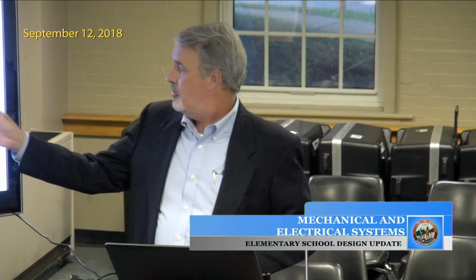Again, an overhaul, an integration into controls. So on those two schools, one of the things we talked about is overlaying a VRF system into the classrooms. Imagine these boxes are classrooms. The unit ventilator would still exist, and in the ceiling would be this device, a cassette, 2x2 or 3x3 box that provides cooling. In years past, if you did cooling like this, every one of these boxes would also have a condensing unit on the roof. Now they're all piped and manifolded to one condensing unit. A contractor is only pulling refrigeration piping through ceilings and tight spaces, not running large ductwork. So it's a great way of adding air conditioning to a space that wasn't originally designed to be air conditioned.